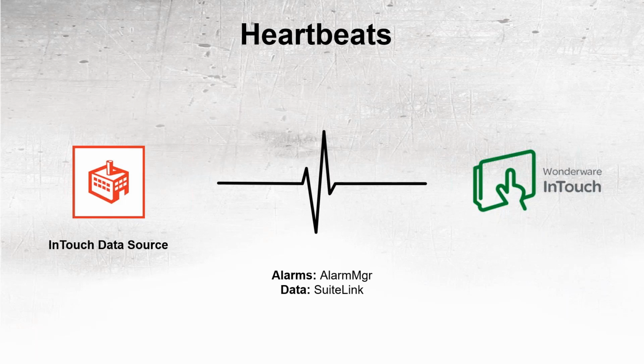We decided to change the way we were interfacing with InTouch because this allows us to have remote connections to InTouch applications, which means you can monitor more than one InTouch application at a time. The problem with the heartbeat, though, is that it's going to go through our SuiteLink connection. And the SuiteLink connection can be good while the Alarm Manager connection could be bad. If the Alarm Manager connection is bad, you're not getting alarms. But if the SuiteLink connection is good, your heartbeat would just keep going and you would think everything's good even though you're not receiving alarms.